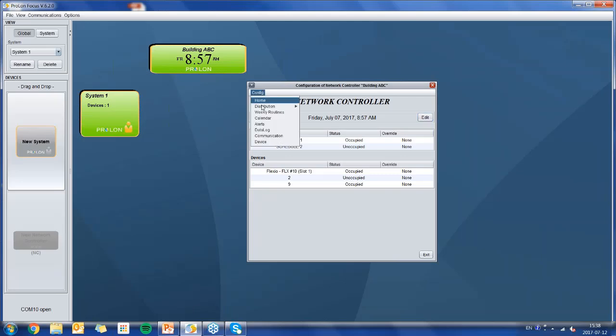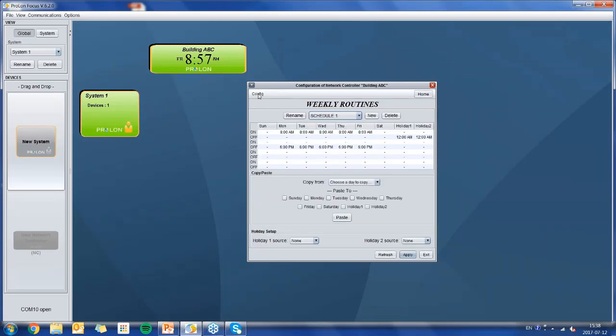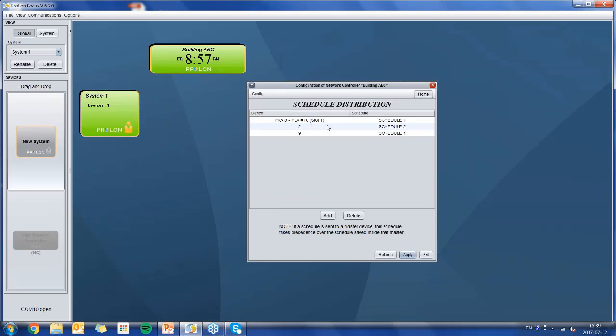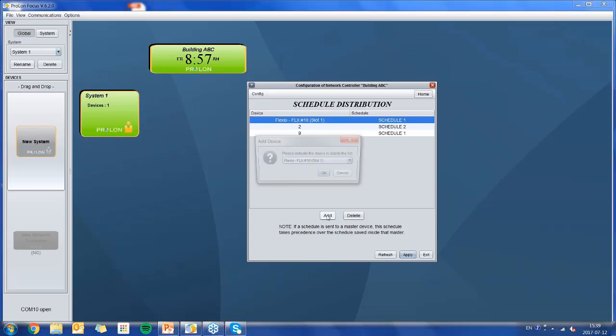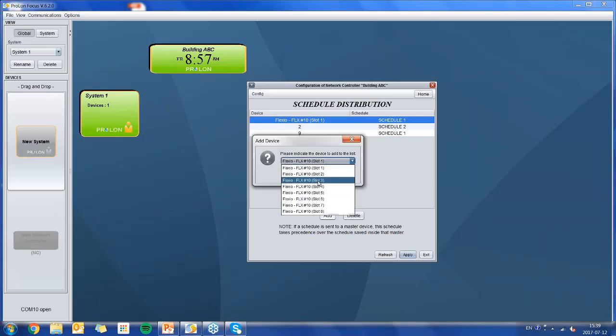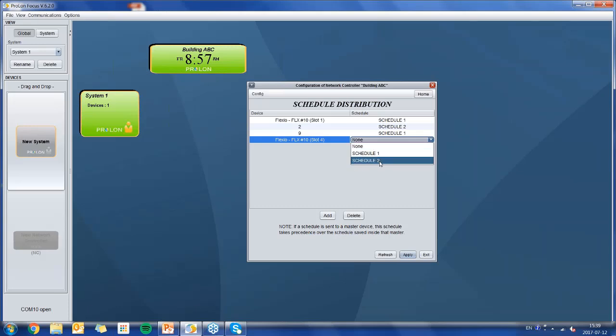As you know, we can make different kinds of schedules; we can handle up to 16 schedules here. So what I can do is, in config distribution, distribute a schedule. When you add a controller, it also includes the FlexIO slots for occupancy. So if I say slot number 4, it's going to follow schedule number 2.